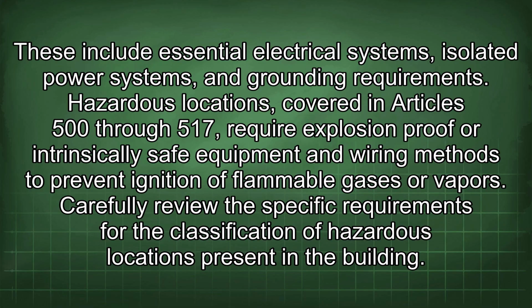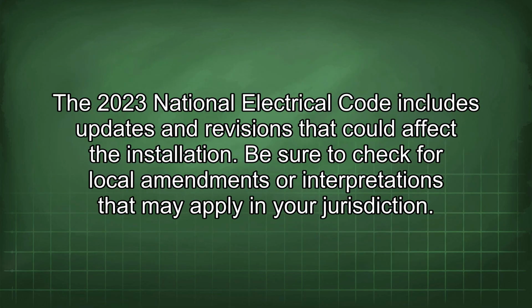Hazardous locations, covered in Articles 500 through 517, require explosion-proof or intrinsically safe equipment and wiring methods to prevent ignition of flammable gases or vapors. Carefully review the specific requirements for the classification of hazardous locations present in the building. The 2023 National Electrical Code includes updates and revisions that could affect the installation. Be sure to check for local amendments or interpretations that may apply in your jurisdiction.